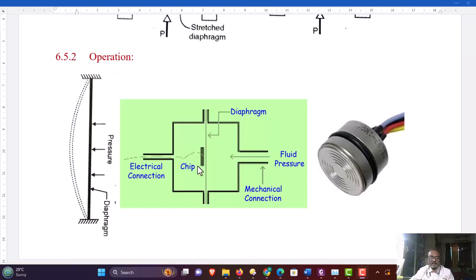The displacement can be measured by a displacement sensor, or by a strain gauge sensor, or by a semiconductor chip sensor. Different principles are employed to measure the displacement of the diaphragm. Let us suppose that we have connected a chip sensor here. Now when the fluid pressure is applied, there is a deformation and deflection of the diaphragm. The deflection is proportional to the applied pressure. Therefore, the chip sensor provides the output proportional to the deflection. The electrical output is available at the output of the sensor.